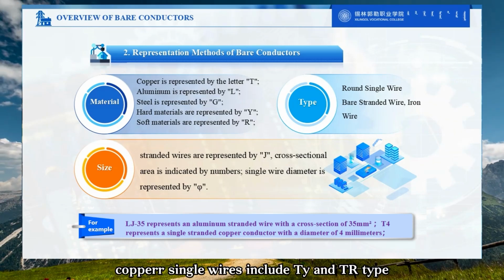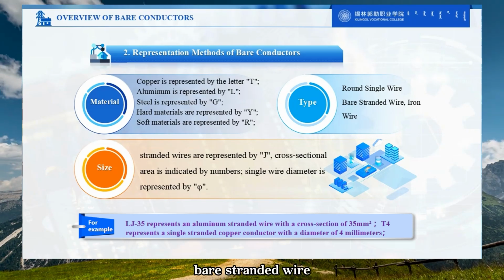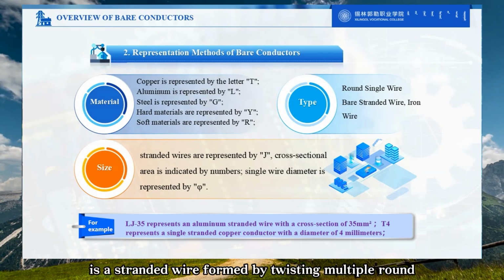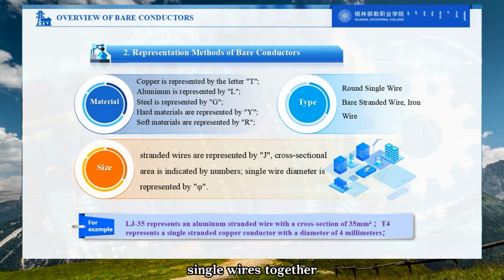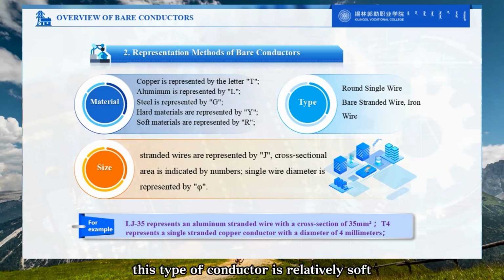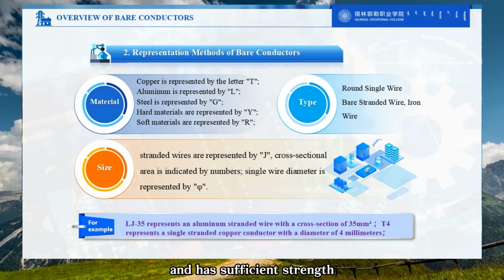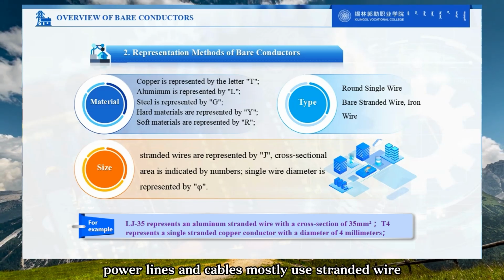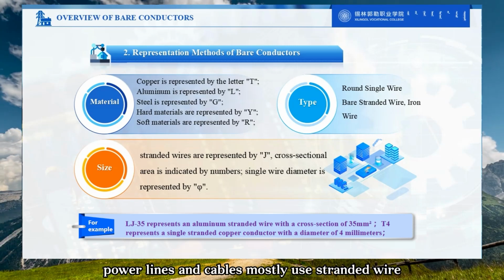Copper single wires include TY and TR types. Bare stranded wire is formed by twisting multiple round single wires together. This type of conductor is relatively soft and has sufficient strength. The core wires of overhead power lines and cables mostly use stranded wire.